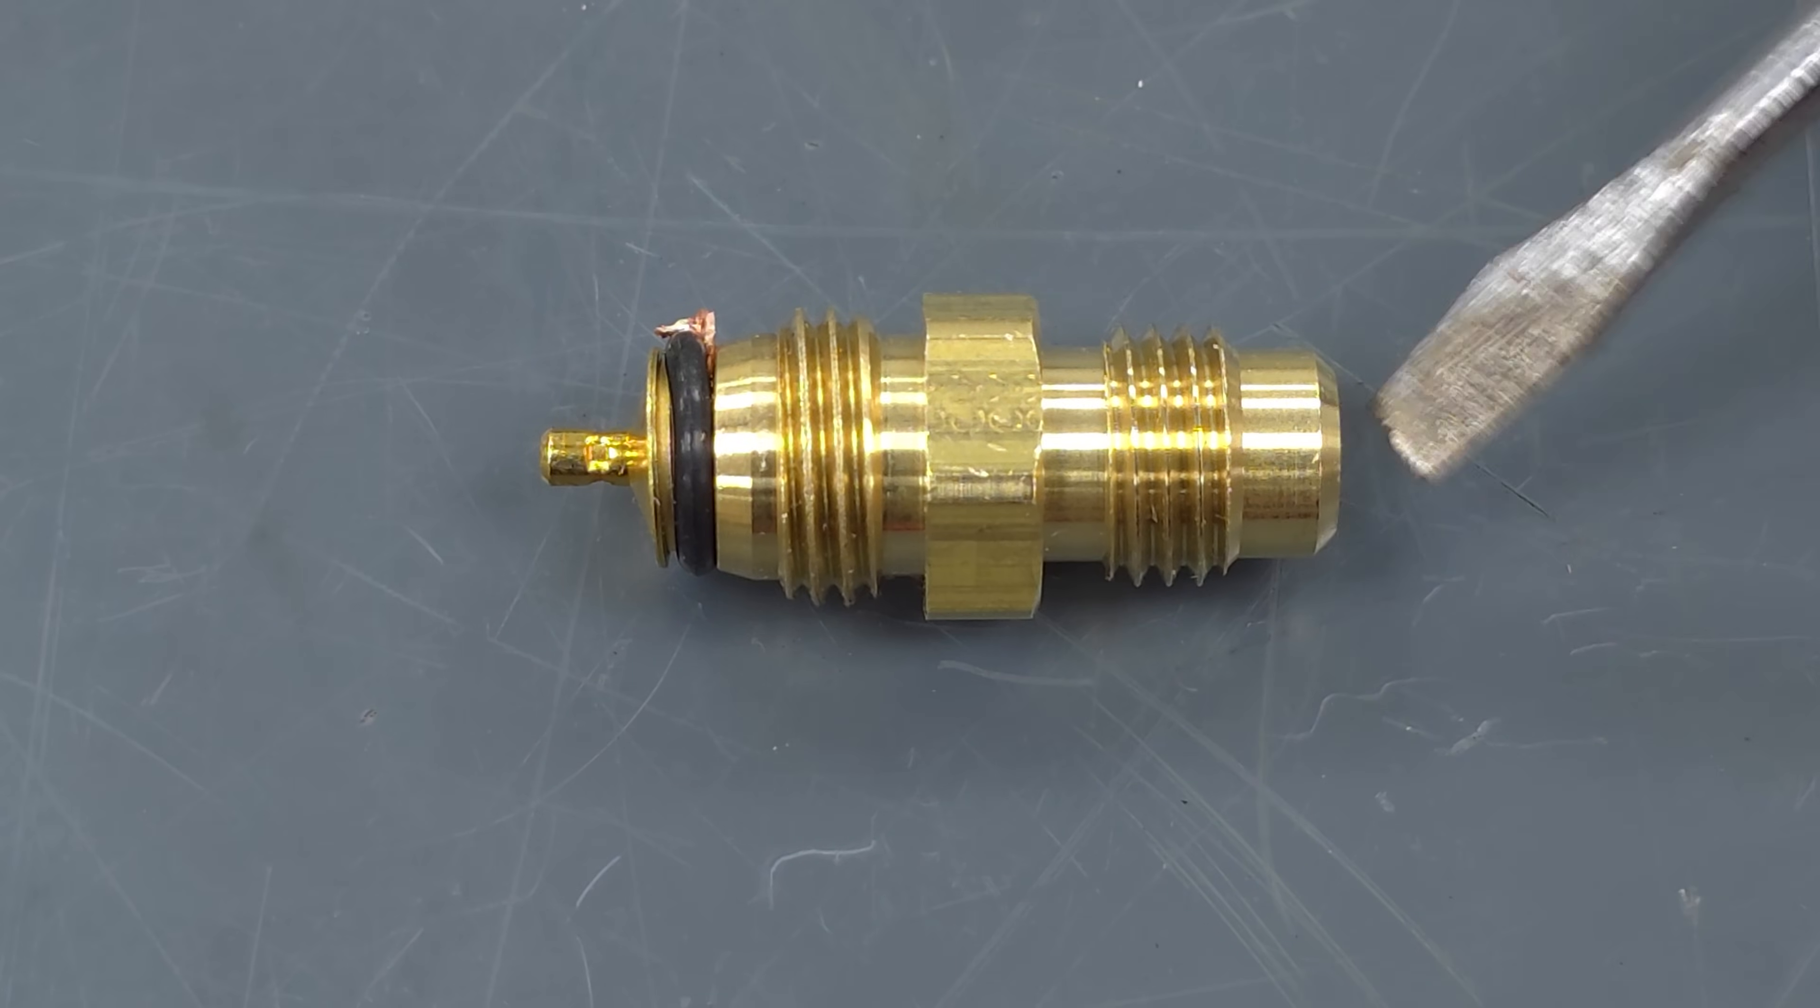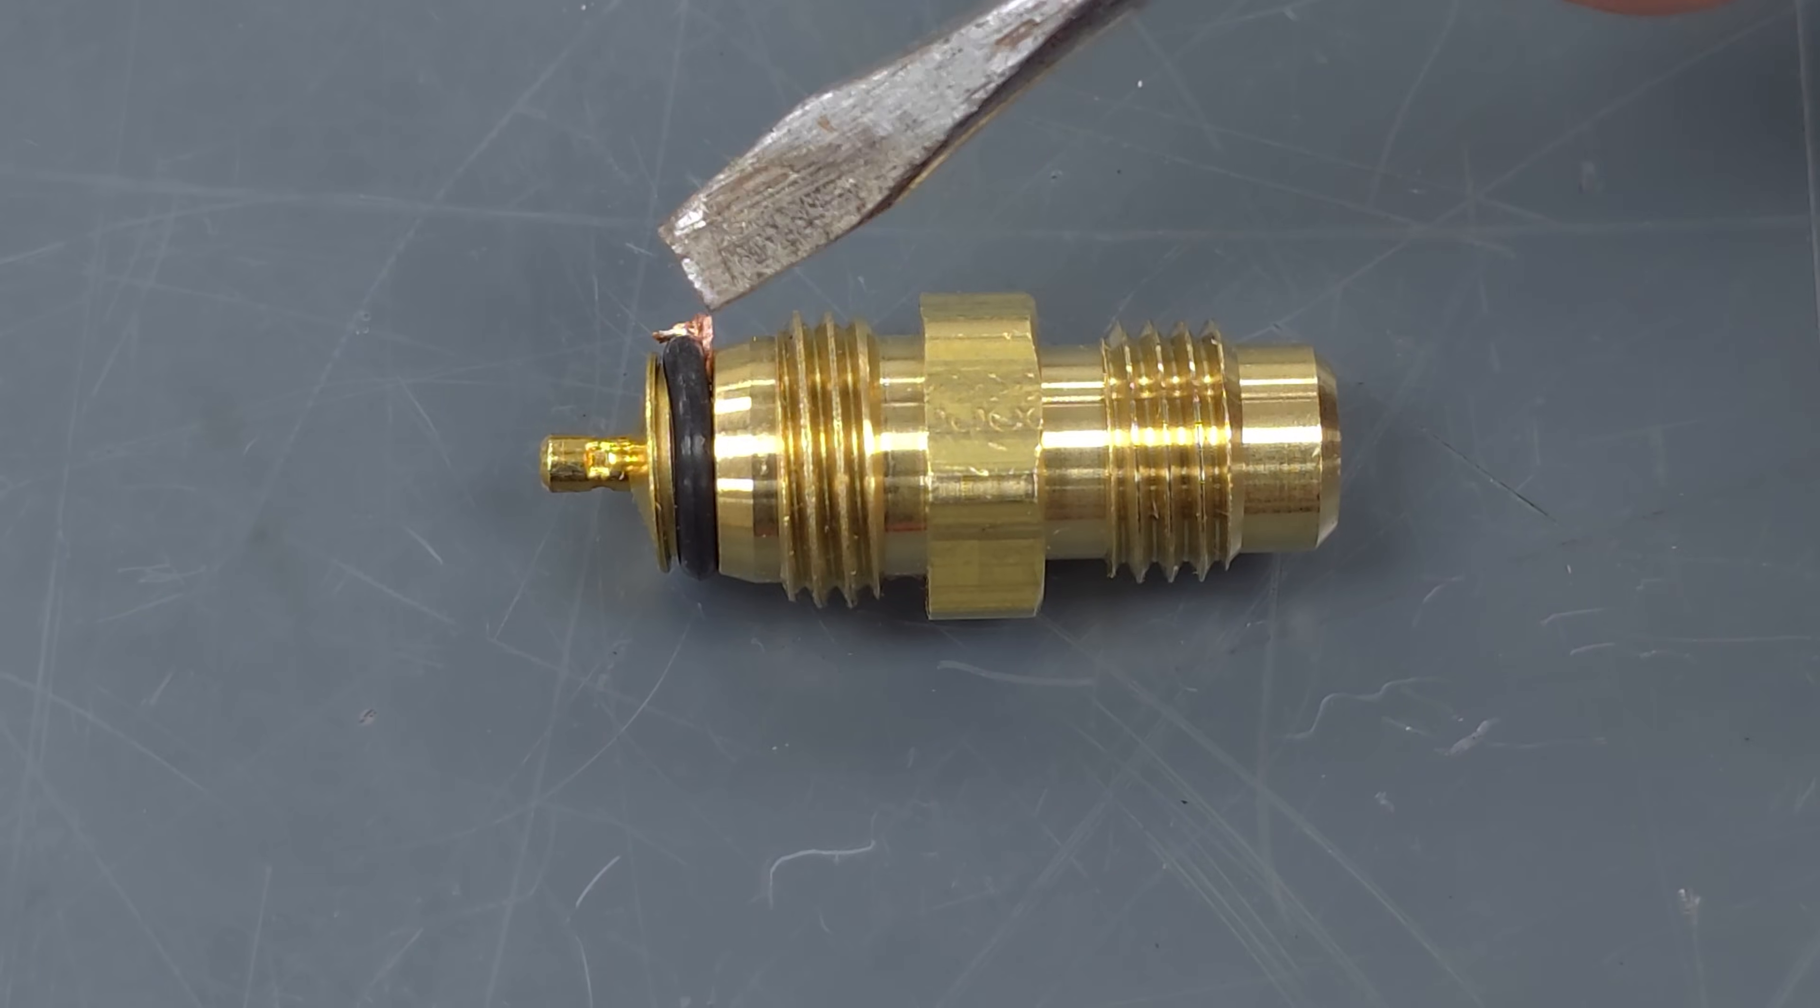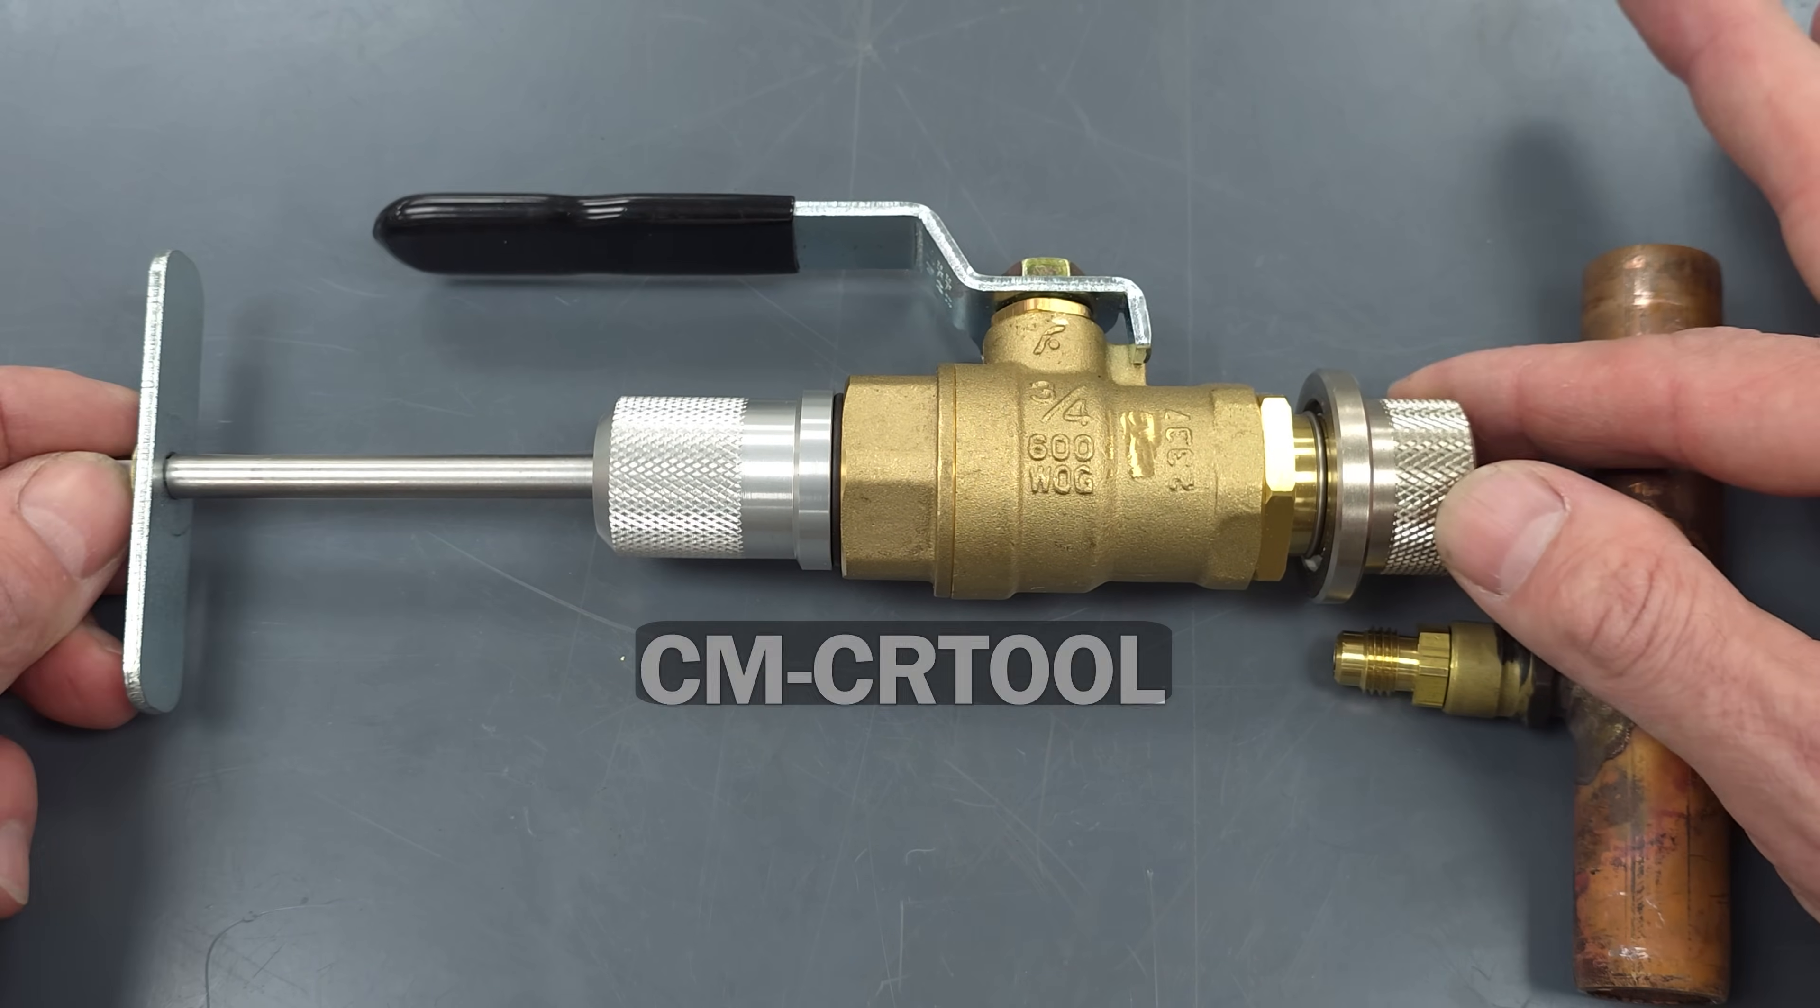Now that we showed how the Cormax valve assembly works if you have some type of a leak over here at the port maybe due to like a copper shard or something like that stuck up against that rubber grommet I'm going to show you how to replace this even if you have pressure in the system.